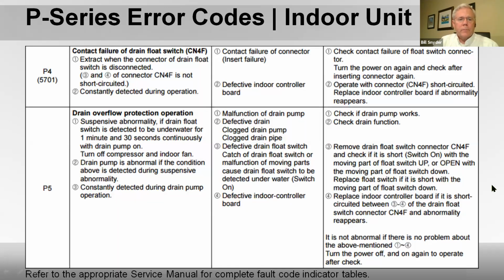You'll probably spot it. There are the 2-digit codes we're talking about, maybe a P5 or P4 error code that shows up on the P series units. Occasionally these codes will show up on an MHK1, that's that Honeywell type thermostat, on an M series, but they won't typically be in the M series book. You have to go by the blinking LEDs to determine what's wrong on the M series. The P series sometimes will give you a 2-digit code like this. So it's kind of telling you where you might look, like drain overflow protection, and it'll tell you what may cause it, what a possible solution is, how to fix it.